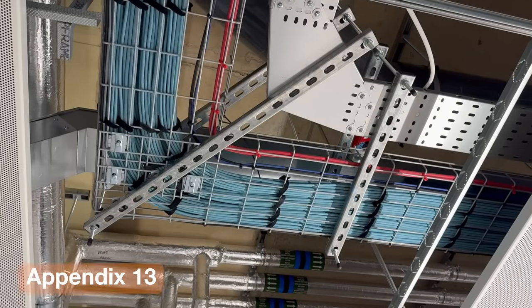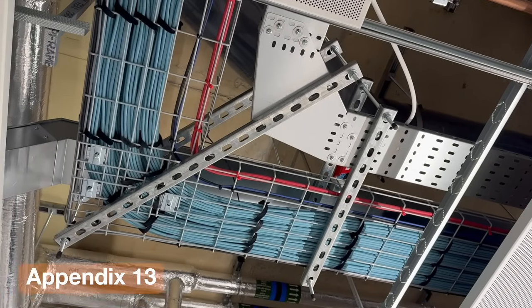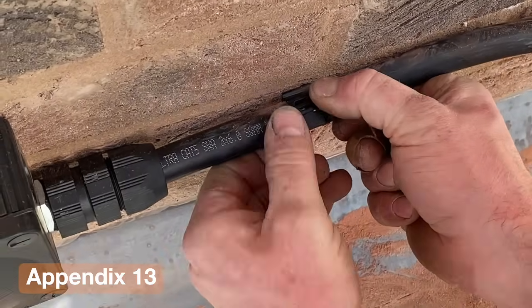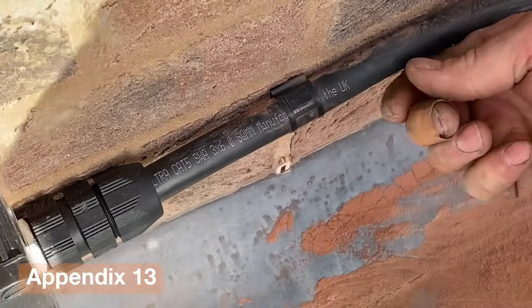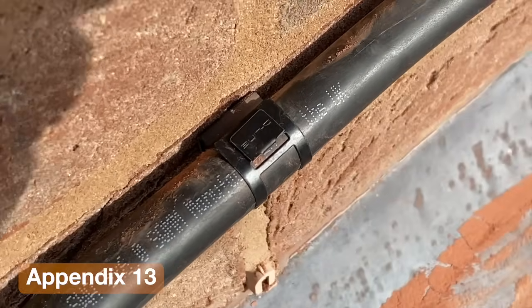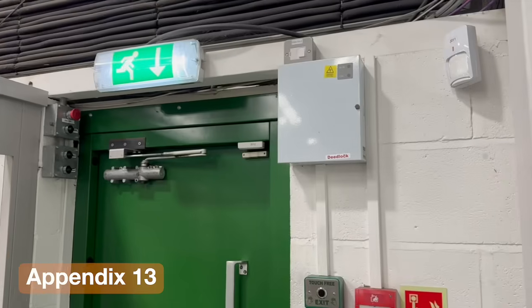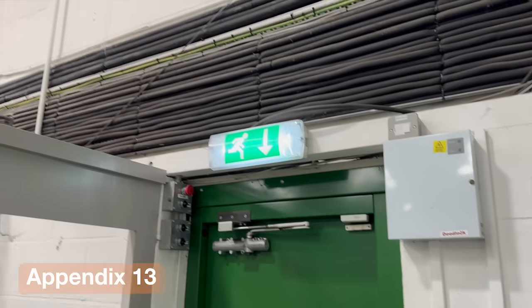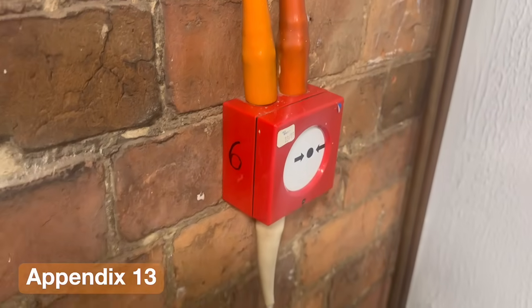Cables in escape routes must not significantly add to the fire load, they must not emit large amounts of harmful gases, and they must not collapse onto occupants or firefighters. So in practice, this drives the use of metal fixings, fire-rated supports and appropriate containment systems. As you move into protected areas, the requirements become more restrictive. Only systems related to fire safety should be present, such as emergency lighting or fire detection.